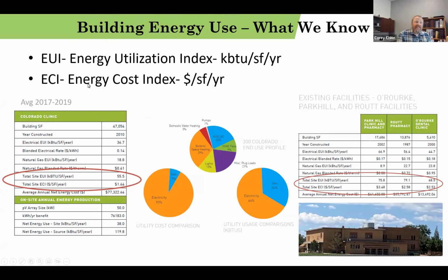And then we have energy cost index, which is dollars per square foot per year. This is the real tangible piece. And oftentimes in our world, people are getting, in my opinion, too caught up in energy or carbon, and they don't look at the cost. If we're gonna help people, it's important that we look at all three legs of this stool. And if we reduce cost, we are directly helping people. So we know ground source heat pump is a great opportunity to reduce cost and energy.